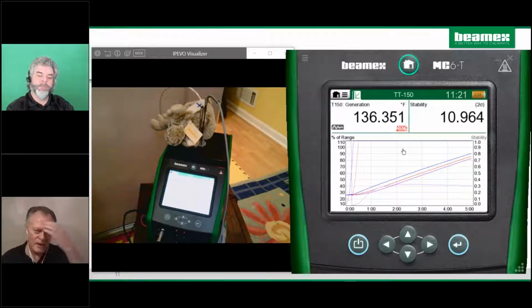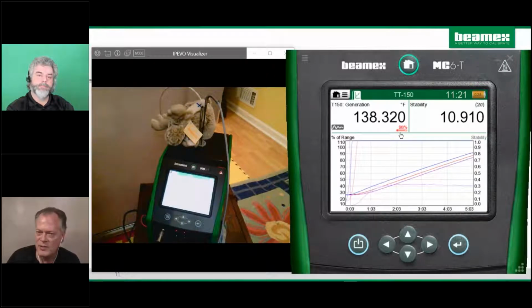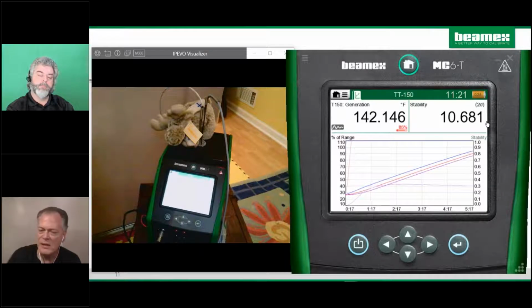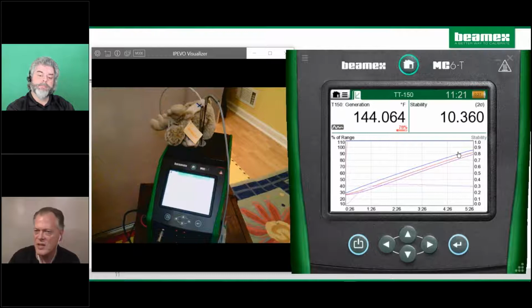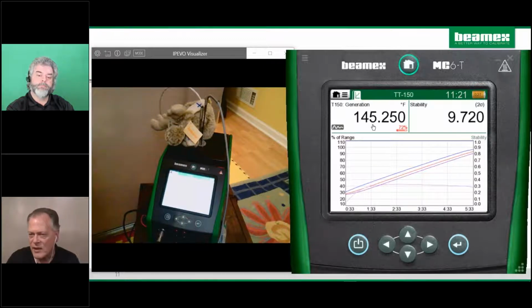Okay. And there's another thing that we're showing here. This is showing the actual temperature measured by the internal control, but we also have this 2 sigma calculation going on. So we're looking at stability. This is like a 2-minute integration of the readings, and it's a delta of 10 degrees. So going back 2 minutes, it was 10 degrees lower than it's seeing now. But as we get closer to 150, and these 3 lines start to flatten out, the stability number is going to drop. And in fact, we want to see it below 1.